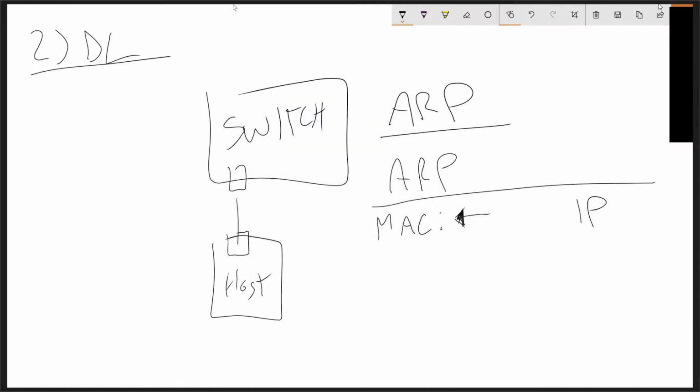So what happens is that this port knows that the MAC address is assigned to this port and assigned to this IP address. That'll become very important when we move into layer 3 a little bit later, because this is how the resolution of IP addresses is done. But the big thing here is that you've probably heard the term MAC address on BACnet MSTP before. That's because BACnet MSTP is a data link layer, and it is also using a MAC address for its addressing, albeit not using Ethernet, it's using MSTP.